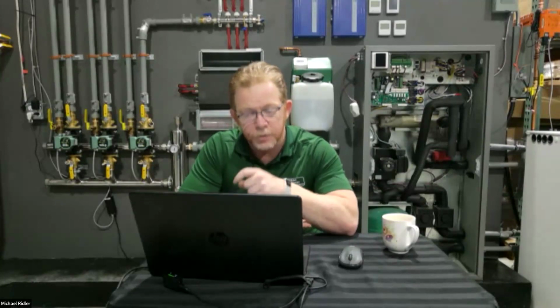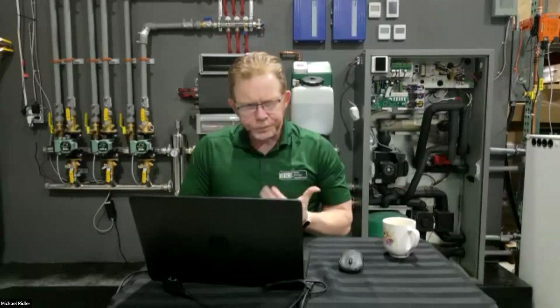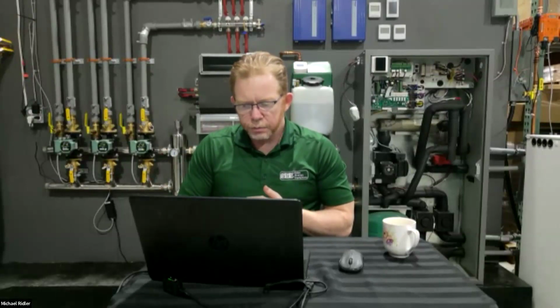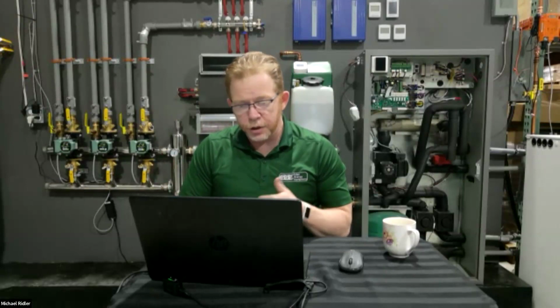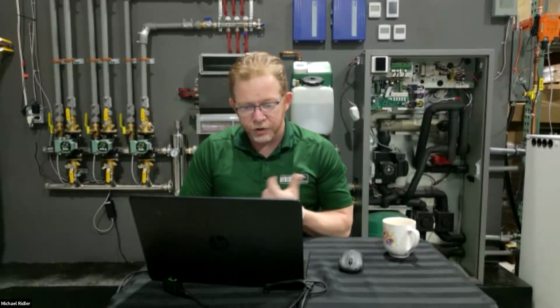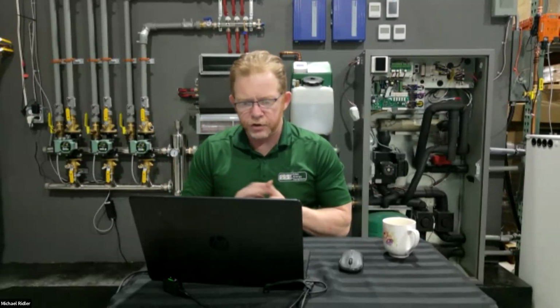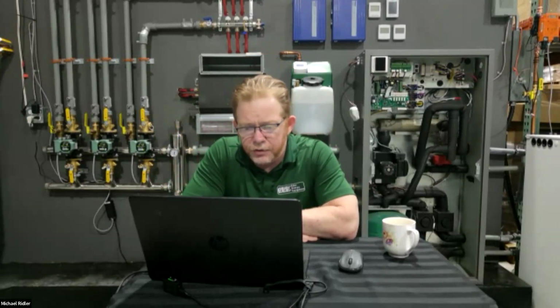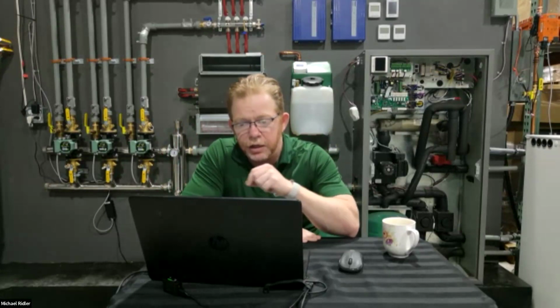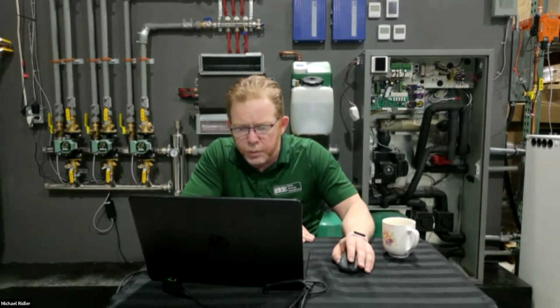With a PCM battery, you have to pick it for a specific temperature. You can exceed that temperature—so if you pick one designed for 140, you can feed 170-degree water into it, but you can't feed 130 into it. If you put 130-degree water into a PCM battery, it's not going to phase change. An indirect is a little similar but more forgiving—you'll still have some hot water because you have a lot of water storing it. The advantage of the PCM battery is its ability to store sensible and latent energy, which we can't do with water-based storage.